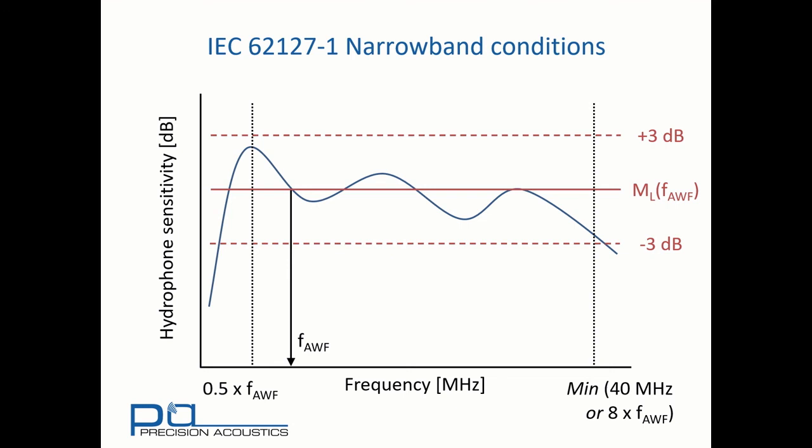The narrowband condition requires that within the frequency range from half of the acoustic working frequency to the minimum of 40 MHz or 8 times the acoustic working frequency, there is no more than plus or minus 3 dB variation in the hydrophone's response, where the zero reference point is taken as the sensitivity at the acoustic working frequency.